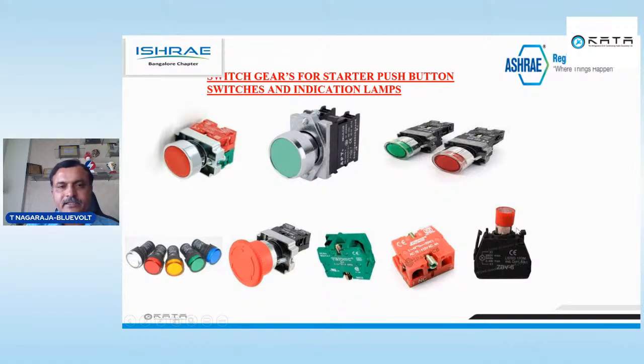These are lamp holders. Some push buttons will be illuminated push buttons. This lamp holder will be placed behind the push button, so that whenever you press the button, the light will glow in the push button itself. Those are called illuminated push buttons. These are normal push buttons. This is an emergency push button. Whenever you press it, your contact will open, and whatever the circuit, it will be switched off. The same push button can be lockable also.